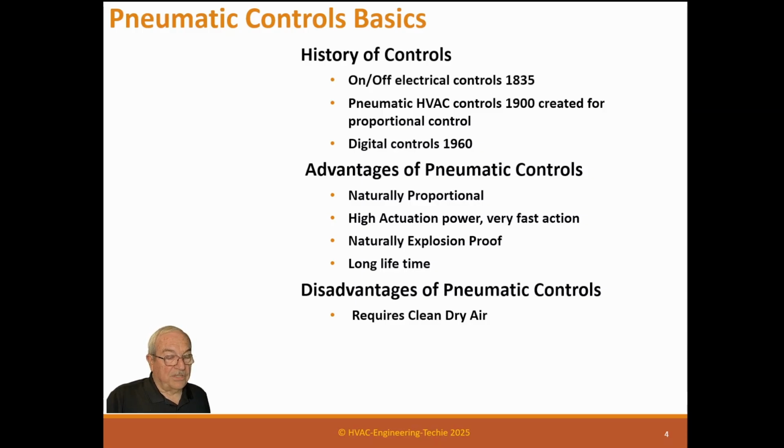I remember a sad day when I had a hotel call me and say that they have a problem with their thermostats. I said, what's the problem? He says they won't calibrate. I said, what do you mean? Well, you try to calibrate them and they just won't calibrate. I said, when did the water event happen? And they said, oh, well, that was 2 weeks ago. We had a problem with air compressors.